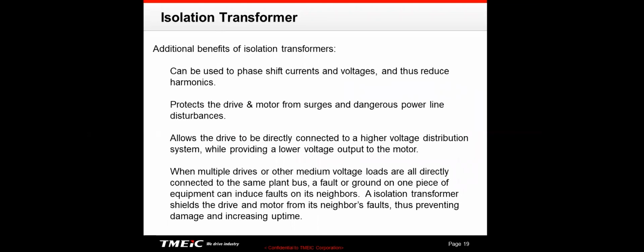Let's look at additional benefits of isolation transformers. Number one, it can be used to shift phases, currents, and voltages and thus reduce harmonics. So if you have a multi-pulse drive, that would be a 12-pulse drive, an 18-pulse drive, a 24-pulse drive, and so on, you really have to have an isolation transformer. Second, it protects the drive and the motor from surges and dangerous power line disturbances.